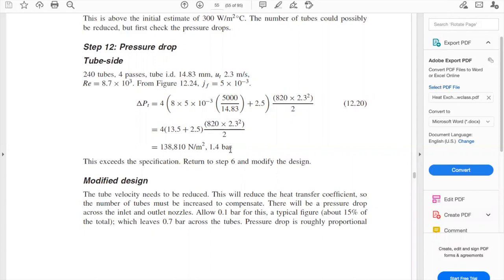It is not allowed because the problem statement says that the permissible pressure drop in both streams is 0.8 bars. So it exceeds the specification required, and we need to return to step 6 and modify the design. We need to go back to step 6 and redo everything until this step. Every single iteration and every single step you go back, you need to put detailed calculations for the new step.